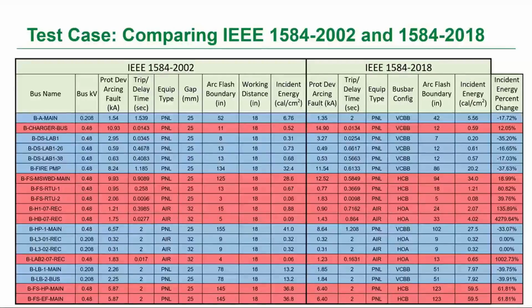Now, if you also look at the blue rows, you can see that for a lot of the vertical bus bar orientations, the energy in the calculations went down. So what was a more conservative calculation used for everything in the previous standard, the 2018 standard attempts to provide a little more accuracy based on the configuration and the other factors.